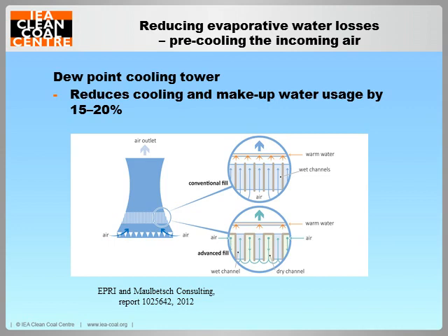Dry channels are incorporated between the wet channels in the tower fill, as shown in this figure. The incoming air is pre-cooled in the dry channels to about the dew point temperature by water evaporation in the adjacent wet channels. The air then passes into the adjacent wet channels where the heat is removed from the water. Now, this system could reduce cooling and make-up water uses by some 15 to 20%. And in addition, power production could increase by up to 4% due to lower turbine back pressure.